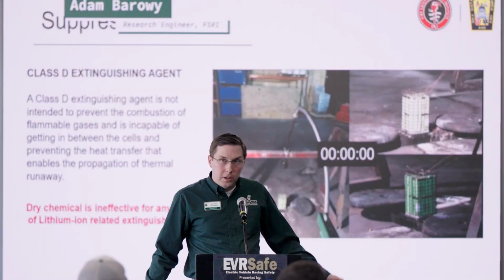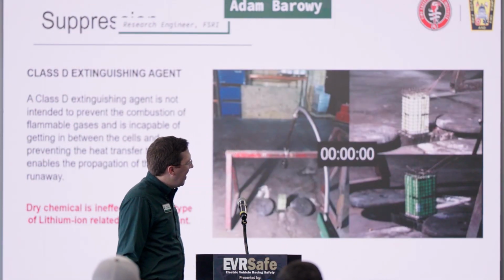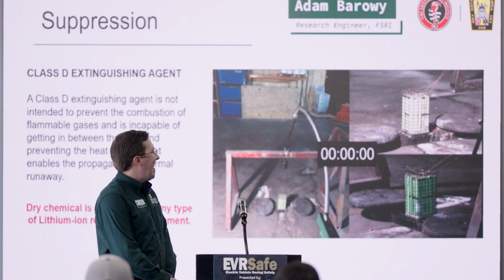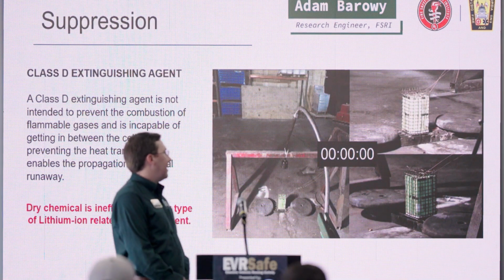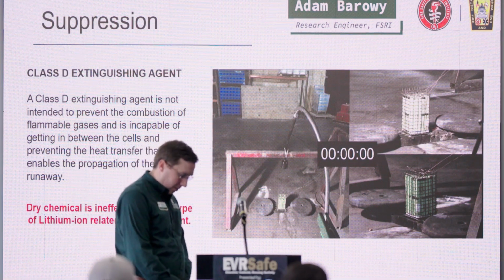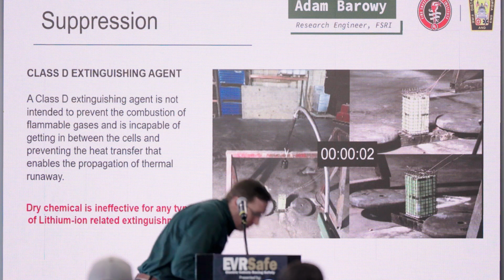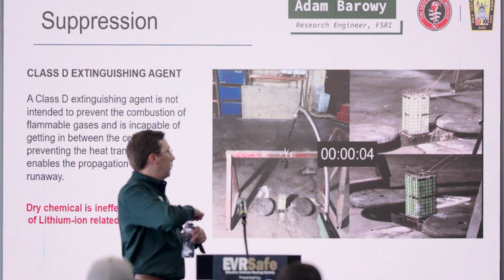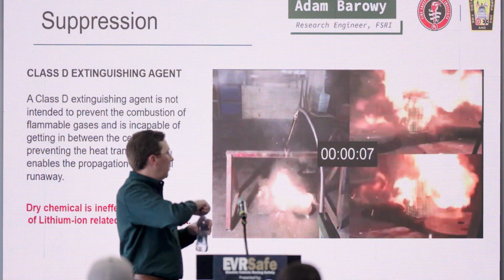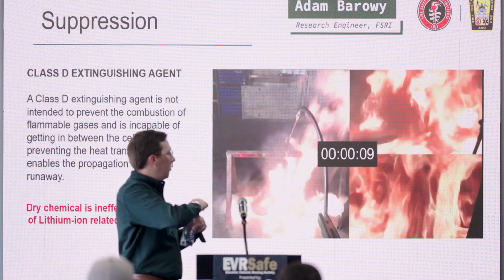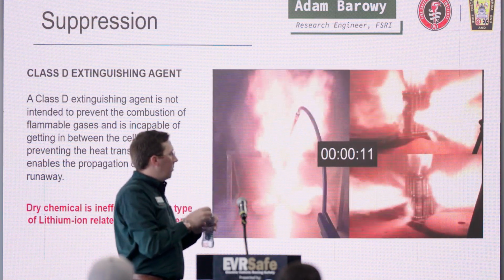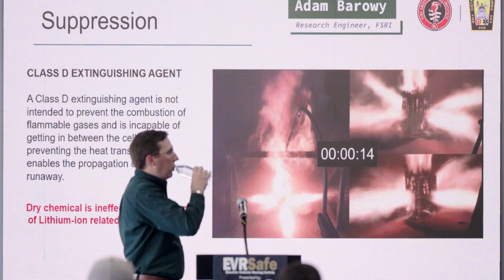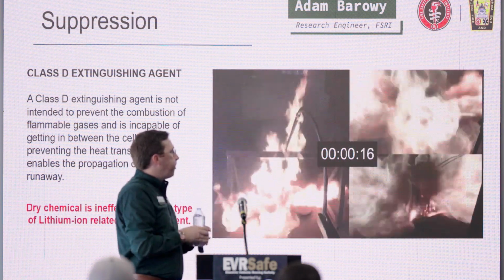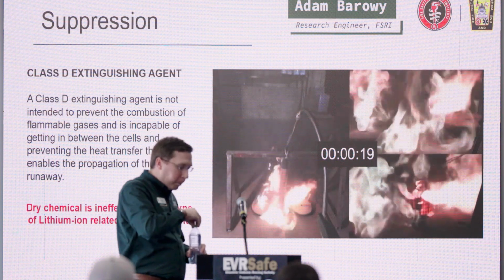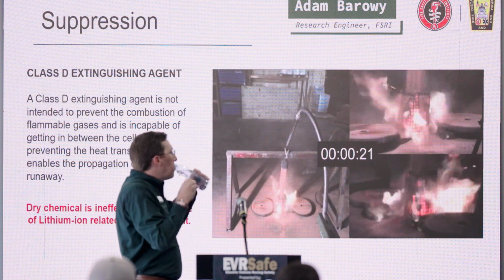And if you need further proof, here's another video. This is Class D extinguishing agent applied directly to a battery pack. The instant it goes into thermal runaway, there's no response time from someone saying 'oh shoot' and then running over to the extinguisher. So here is thermal runaway, and here's the Class D agent being poured right over it. Since Class D agents are really meant to smother and encapsulate burning metals, what you see here is the gases from thermal runaway just pushing that agent out of the way. It can't do its job.